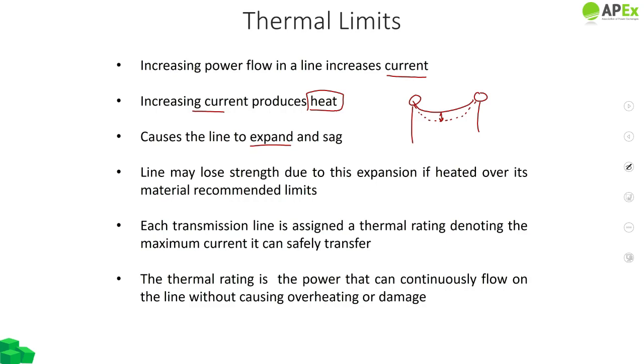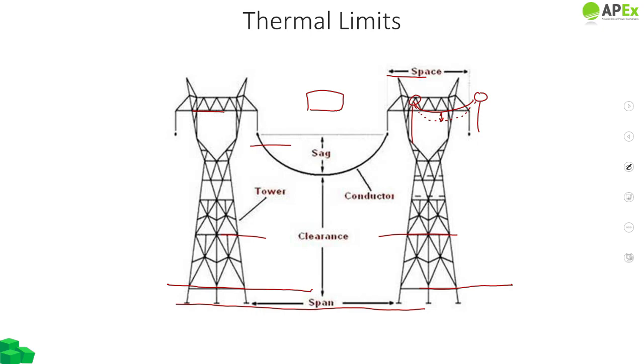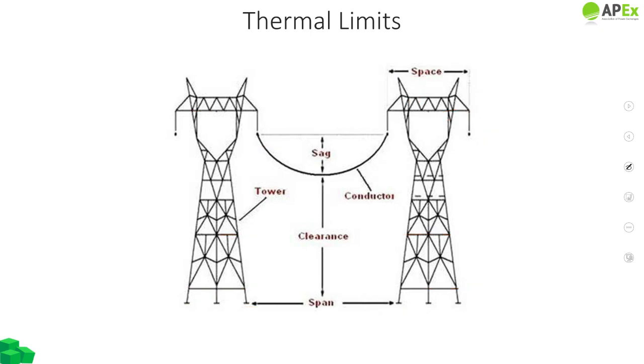Therefore, each transmission line is assigned a thermal rating. And what does the thermal rating show? It shows the maximum current that could be carried safely by that particular line or conductor. So, what is thermal rating in its very essence? It is the rating that shows the power that a conductor can continuously carry without causing overheating or material damage to the conductor. Now let's see this example. We have a conductor between two towers here, right?